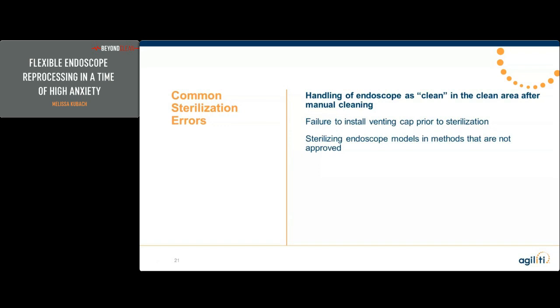And additionally, kind of counteracting this and creating a greater issue, I have found multiple departments that are using low-level quats, which are ammonium-based, to wipe down their endoscopes prior to passing them through to the clean side. And those low-level quats are really made for hard surface disinfection, not for flexible endoscopes, which are really rather porous. And we have no idea what it really does to the materials and their longevity, but there is also no way to tell, since those chemicals are not validated, to know how much residual chemical may be going onto that scope to the patient in the procedure. We don't know what those residuals are and what that could cause.